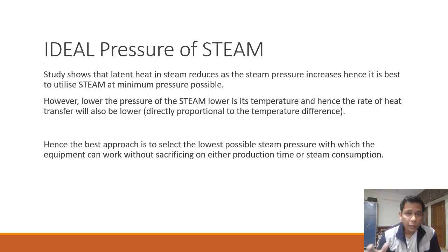Now, when you are using the steam, what should be the ideal pressure of steam? Studies show that the latent heat of steam reduces as the steam pressure increases. Hence, it is best to use steam at the minimum pressure possible.